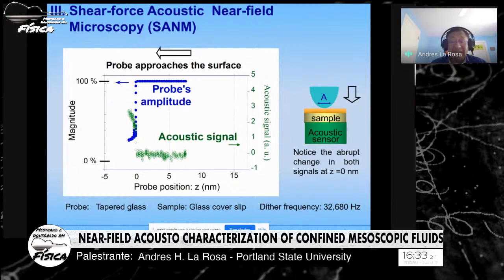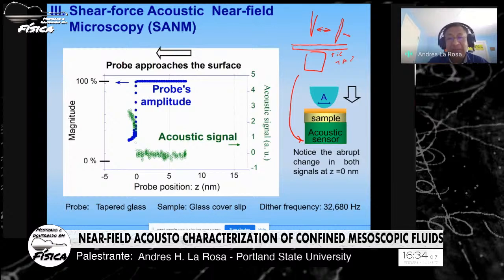So we said, maybe the probe, since we are shaking sideways and they are never perfectly vertical, what might be going on is that when we bring the tip close to the sample, due to this vibration, the tip will be doing tick-tack, tick-tack, because it is tapping on the surface. So that's what we said. If that is true, why don't we put a microphone right there, which is what we did right here? We were aiming to listen to the tapping of the probe against the substrate.